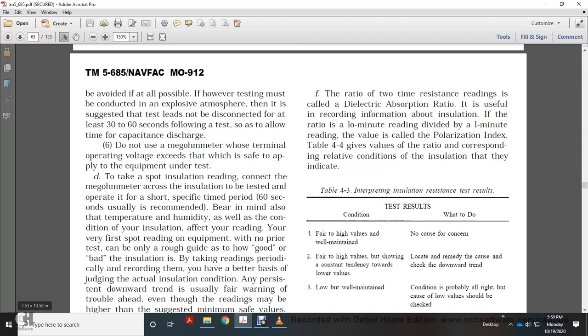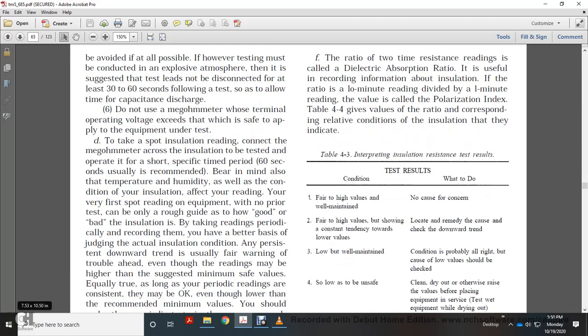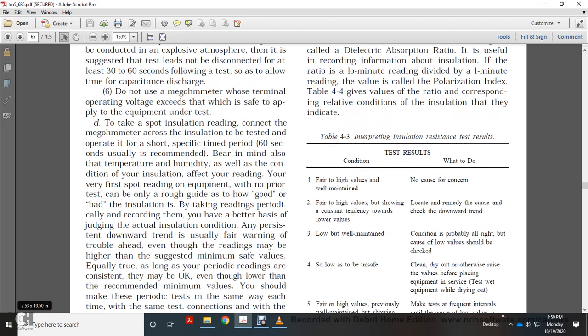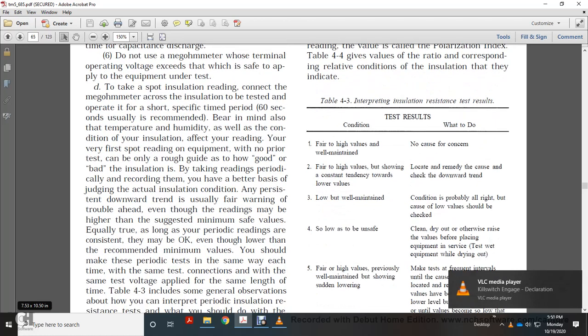By taking readings periodically and recording them, you have a better basis for judging the actual insulation condition. A persistent downward trend is usually a fairly sure warning of trouble ahead, even if those readings may be higher than the suggested minimum safe values. Equally true, as long as the periodic readings are consistent, they may be okay even though lower than recommended minimum values. You should make these periodic tests in the same way each time.